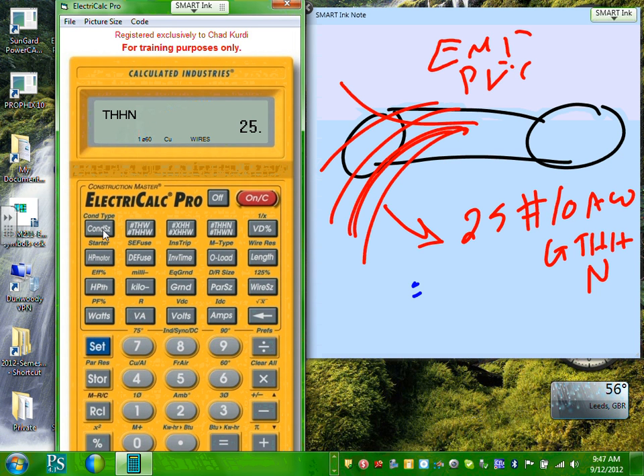Do you see conduit here, guys? Hit conduit. Your EMT conduit, it defaults to EMT. Can you guys see at the top, it is 1.25 inch. Everybody got that one? Now I don't want EMT. If you look at the back of the calculator, it has how to flip them. If you hit set conduit, I need PVC. Can you guys see at the top, set conduit? Where's the PVC? Let's do schedule 80. Everybody can see that set conduit 9 will give you schedule 80.